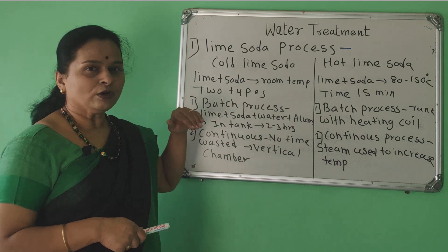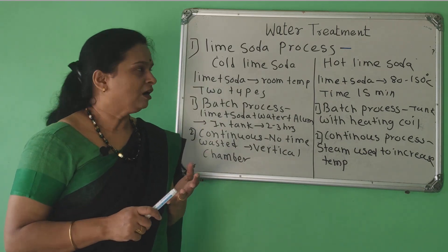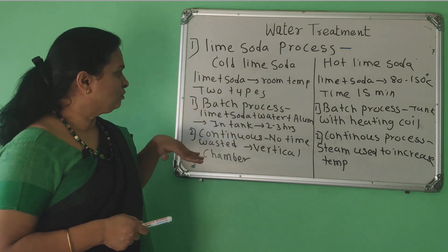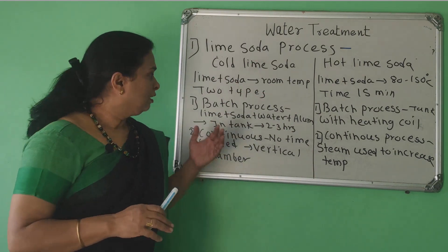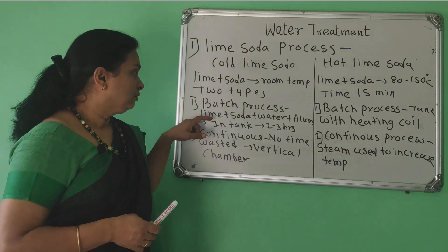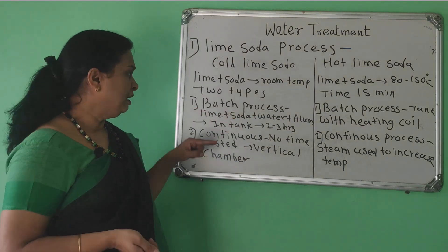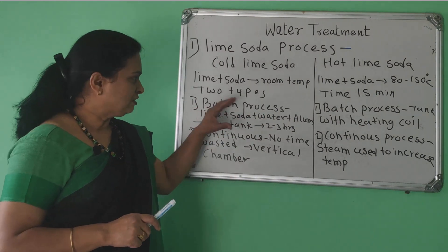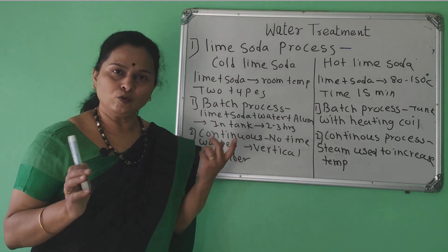In the cold lime soda process, lime soda is mixed with hard water at room temperature. In the batch process, a steel tank of fixed capacity (e.g., 50 litres, 100 litres) is used. Lime, soda, water, and alum — which acts as a coagulant — are added to the tank. Softening the water takes 2 to 3 hours in the batch lime soda process.